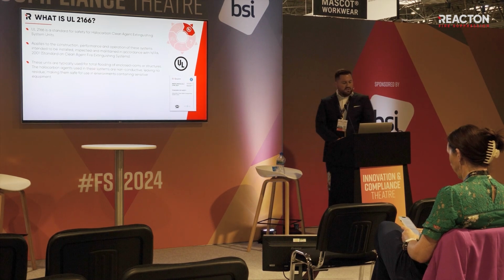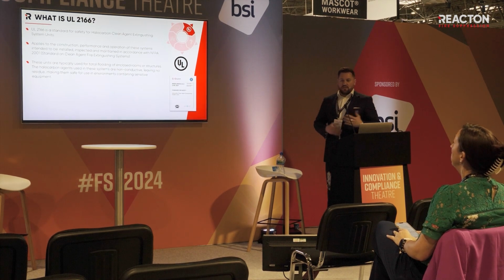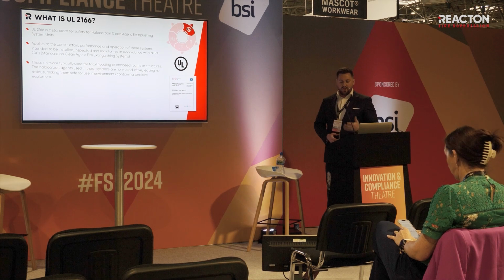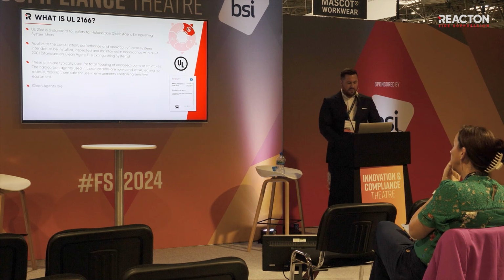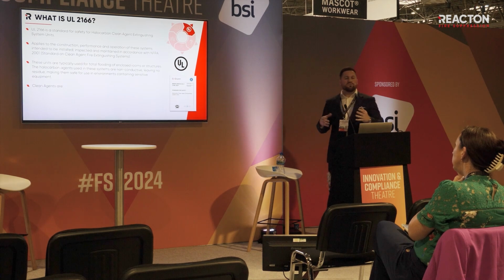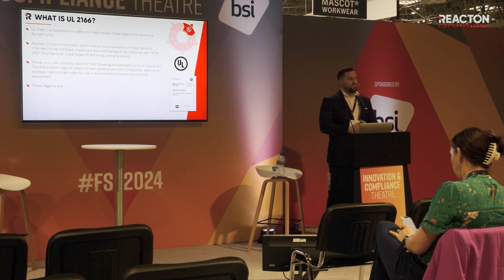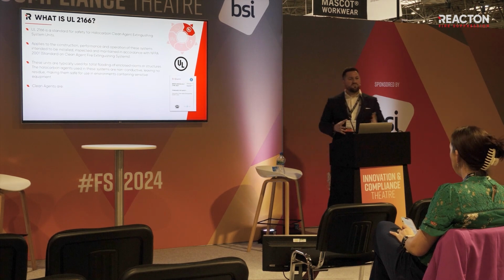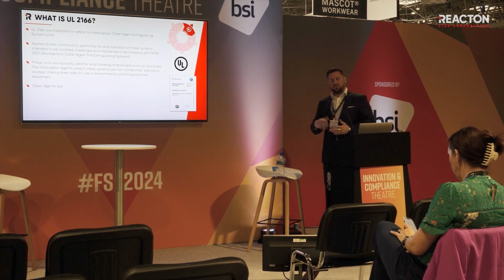Going back to the UL standard, it applies to the construction, the performance and the testing of this extinguishing system. It's put in line with NFPA 2001, and this is what was pivotal to getting this approval. These units are used for total flooding. That means that an agent is introduced into a volume at a specific concentration and it puts out the fire there. They work in a little bit of a different way than some people might be used to, such as dry powders and water mist and those items.